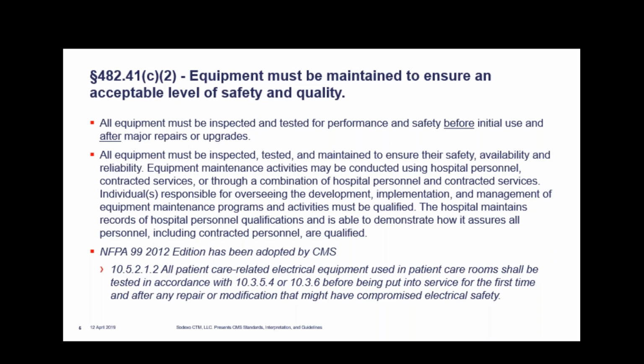Sure. Well, when this came out, it was just adopted, but it's been out for a while. And we immediately put that into our medical equipment management plan. And only unless we see trends that dictate that the device would need an electrical safety inspection during the preventive maintenance. So how many people are aware of this? How many people actually knew that you no longer have to do electrical safety inspections during the PM? Now the question is, how many people are actually putting that into the process, into the program? Well, congratulations.